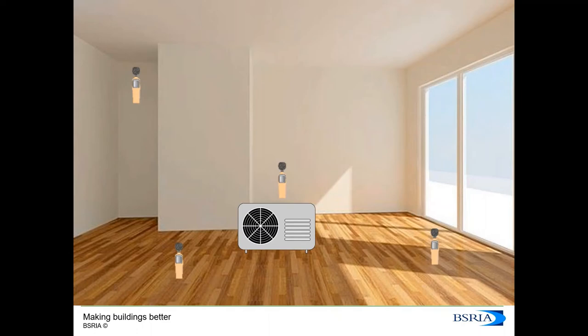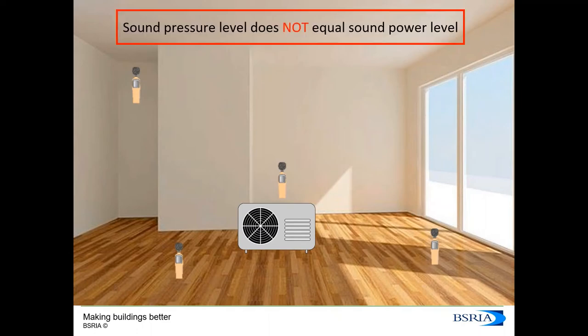Both sound power levels and sound pressure levels are presented using the decibel unit, which can cause confusion. It's important to remember that sound pressure levels do not equal sound power levels — they are two different parameters. Sound power levels are independent of the acoustic environment and therefore useful for comparing two products, while sound pressure levels are dependent on the specific acoustic environment and useful for determining compliance on site or dealing with noise complaints post-installation.